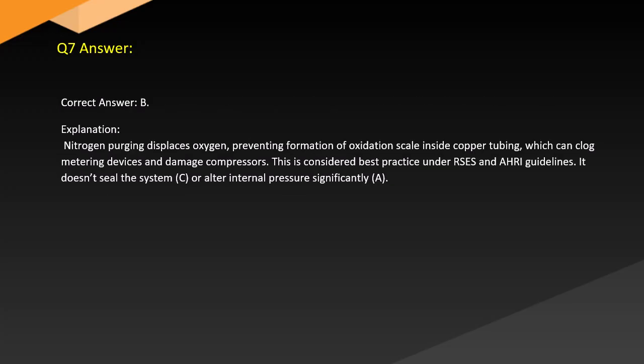Answer. Correct answer: B. Explanation: Nitrogen purging displaces oxygen, preventing formation of oxidation scale inside copper tubing, which can clog metering devices and damage compressors. This is considered best practice under RSES and AHRI guidelines. It doesn't seal the system, C, or alter internal pressure significantly.